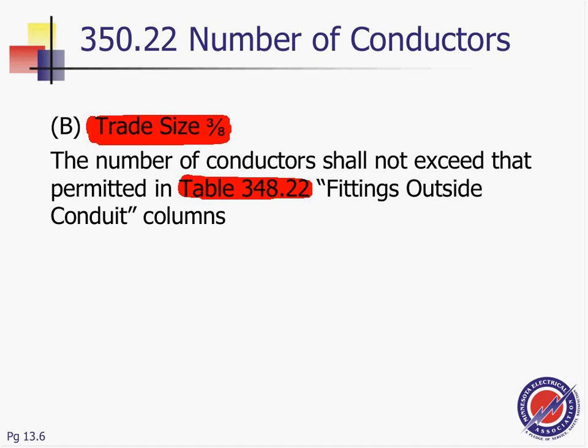And very important, highlight this one for your own sake. They want you always to assume that the fittings are outside, because that's the situation with Liquidtight. The fittings are always outside of it. Very important: fittings are outside. When we go to this table, I'll show you what that means. You want to assume by code, if it's Liquidtight, the fittings are always outside. Now they catch you. This is trade size 3/8 inch. You can fit.